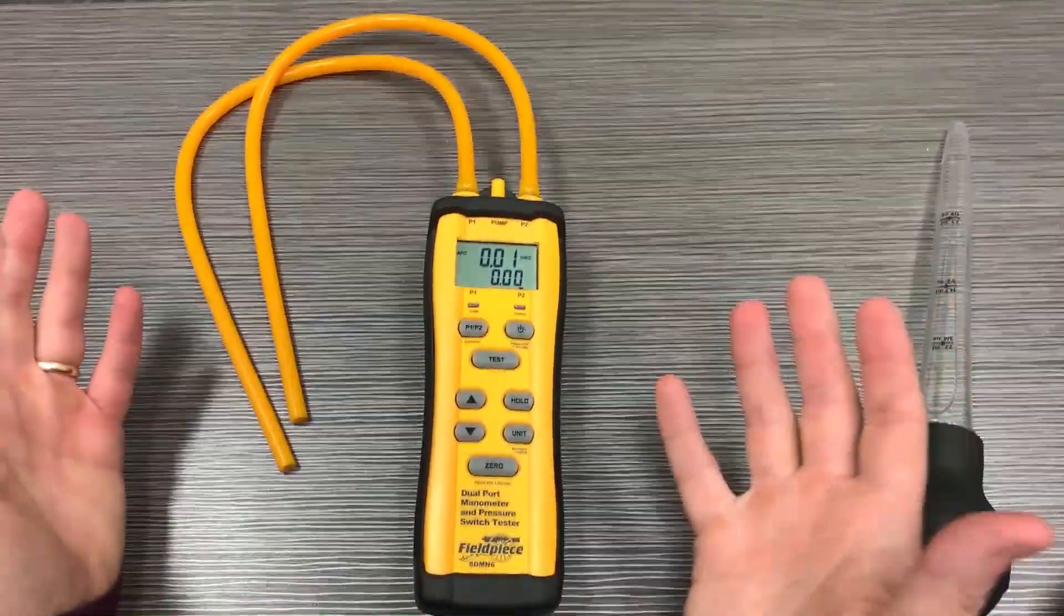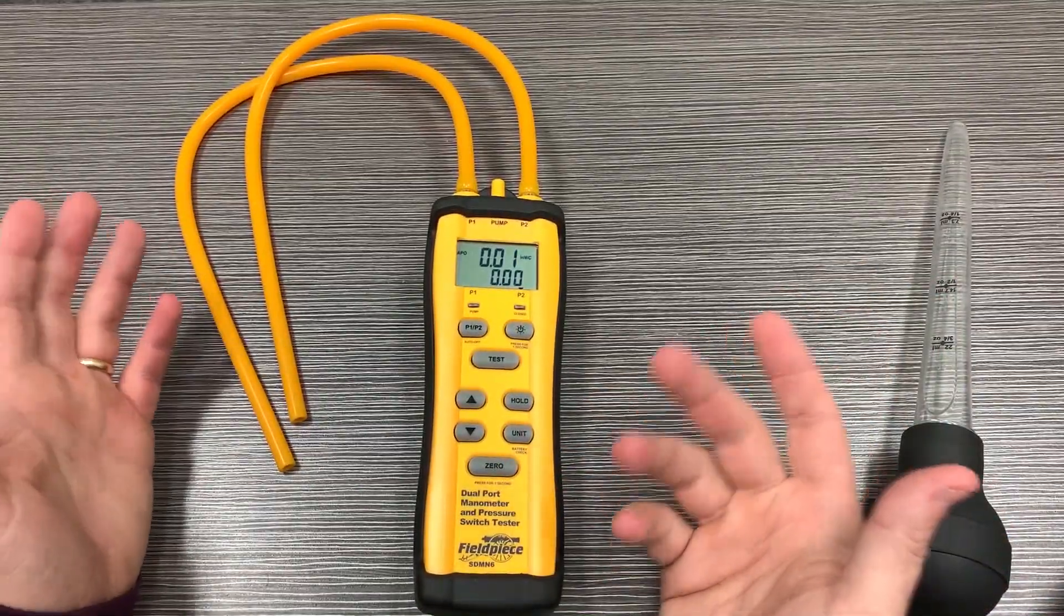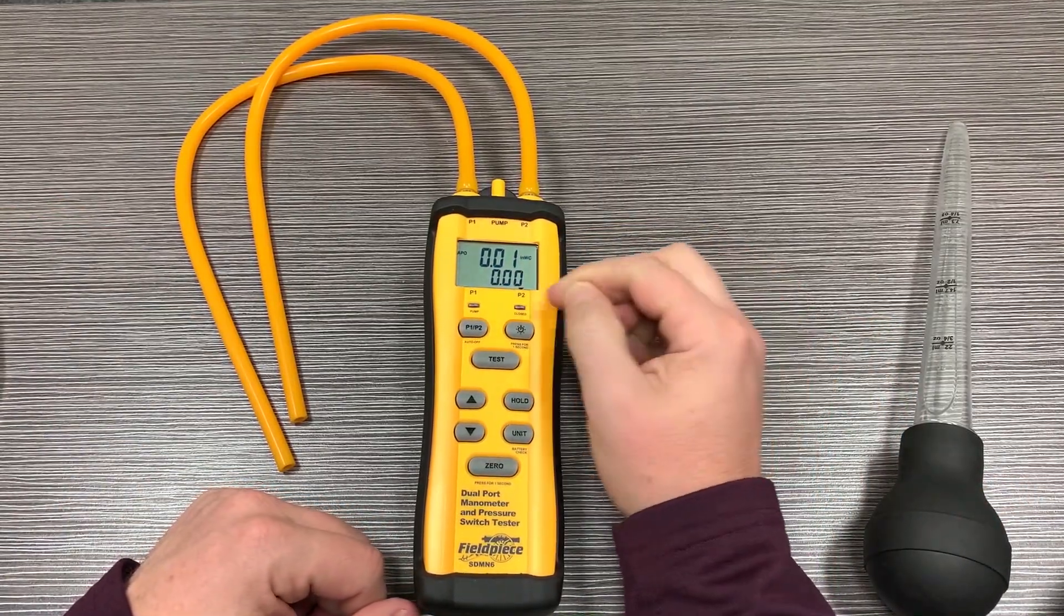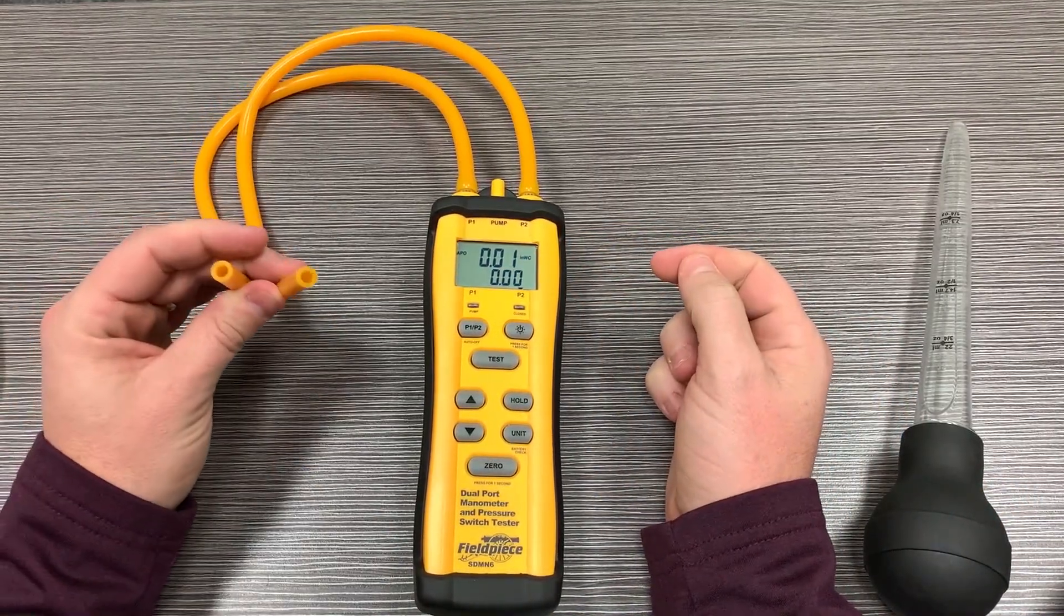All this matters because you have to know what you're looking at. If you're measuring something like total external static pressure, you would want to be looking at the bottom number because that's going to show you the differential between both of them.